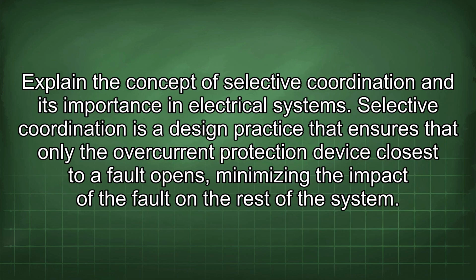Explain the concept of selective coordination and its importance in electrical systems. Selective coordination is a design practice that ensures only the overcurrent protection device closest to a fault opens, minimizing the impact of the fault on the rest of the system.